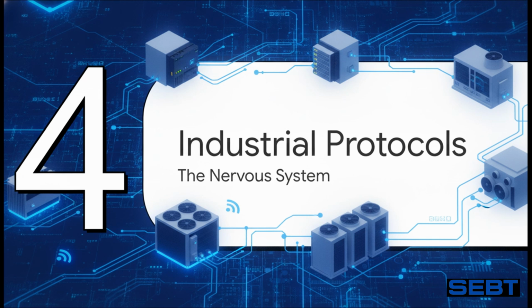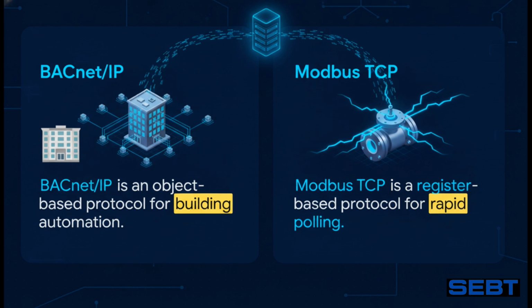This is the nervous system connecting all our layers. To actually share all these amazing deterministic calculations, our PLC typically uses one of these two major protocols to talk to the BMS server. Over on the left, we've got BACnet/IP. This is heavily used in building automation. It's a standardized, object-based protocol which just makes it incredibly robust for managing complex building data, things like schedules and alarms.